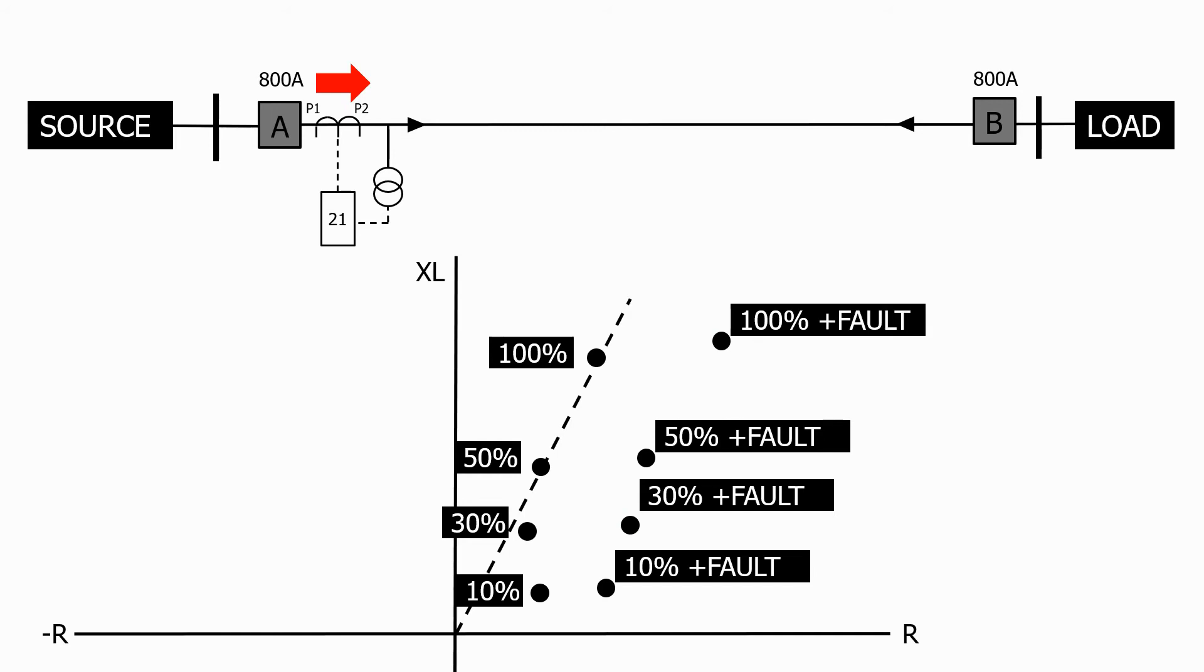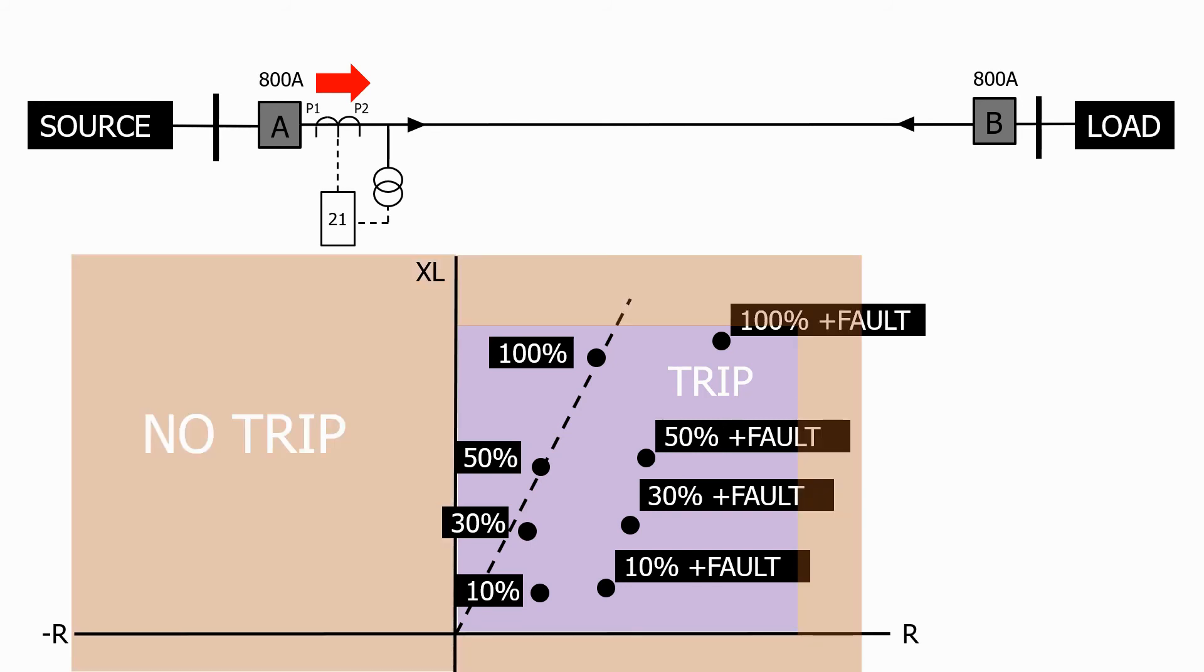We now have multiple possible impedance values for a fault on the line. So how do we set up our impedance relay to operate for all of these different values? Well, the normal way is to set up an impedance operating zone. Inside the zone, we know that the fault is on the line that the impedance relay is protecting. And for any impedance value inside this zone, the relay will trip the circuit breaker, removing the fault from the system. Outside the protective zone, the relay will not operate.